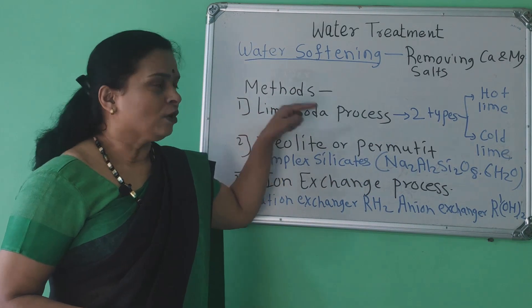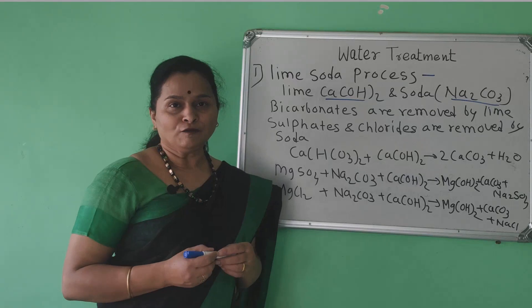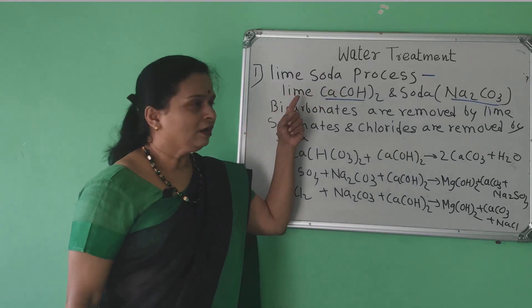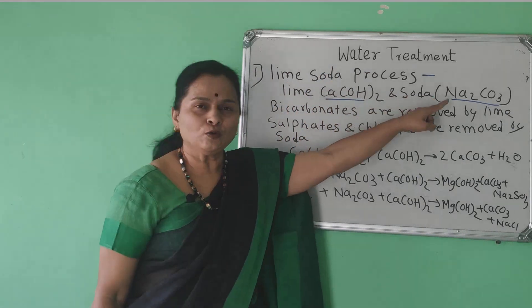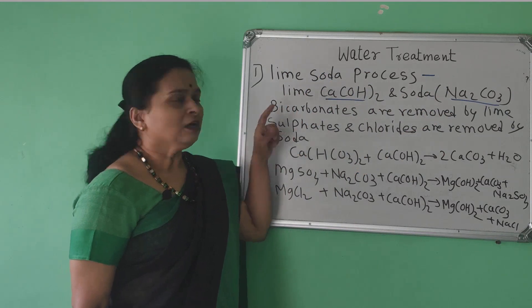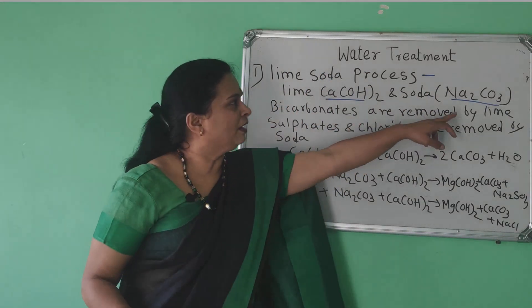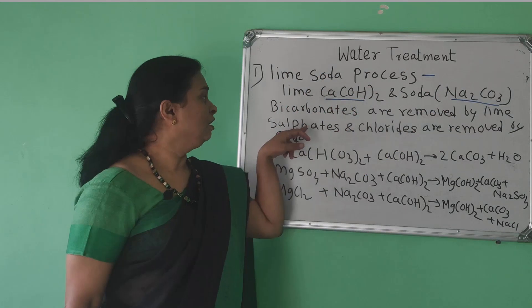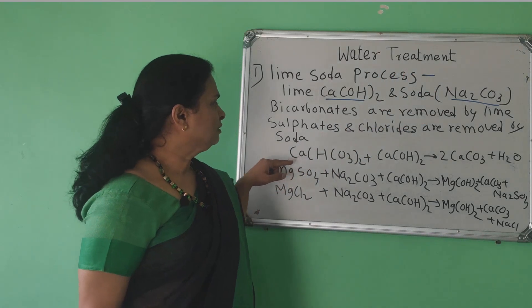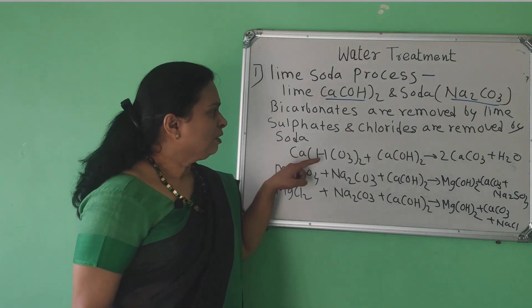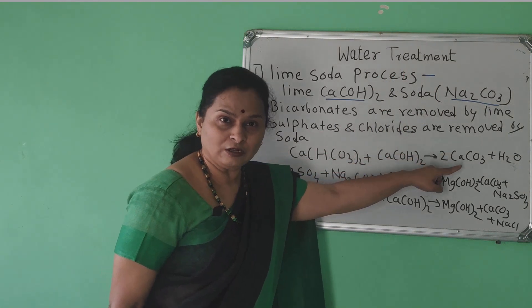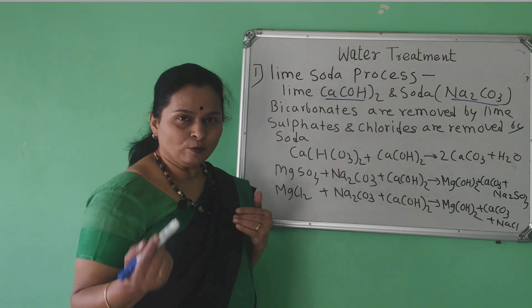The first process of water softening is the lime soda process. In this case, lime (calcium hydroxide) and soda (sodium carbonate) are used for softening the water. Bicarbonates of calcium and magnesium are removed by lime, while sulfates and chlorides are removed by soda. When lime is added to calcium bicarbonate, insoluble calcium carbonate is formed, which can be removed by filtration.